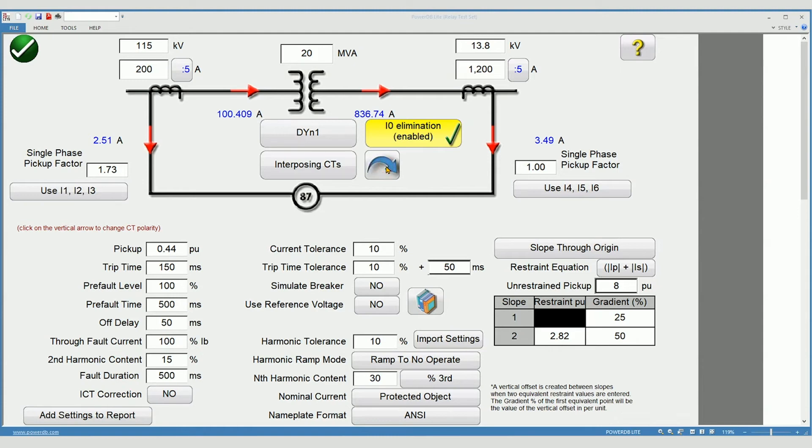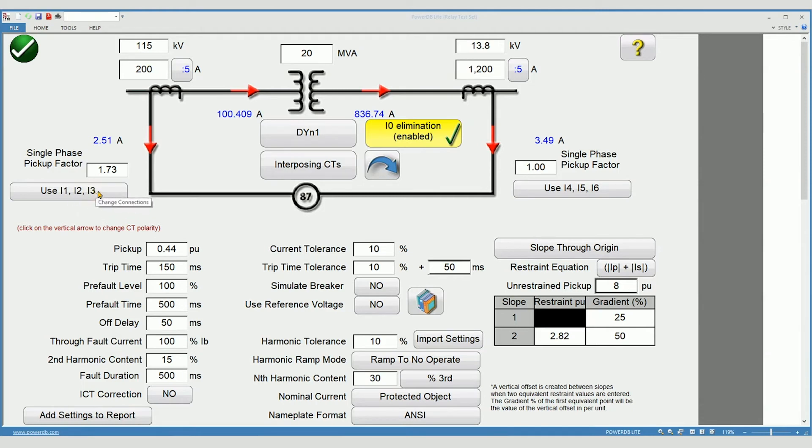You'll be using six current channels to test the relay. By default, current channels 1, 2, and 3 are used to test winding 1. Current channels 4, 5, and 6 are used to test winding 2.